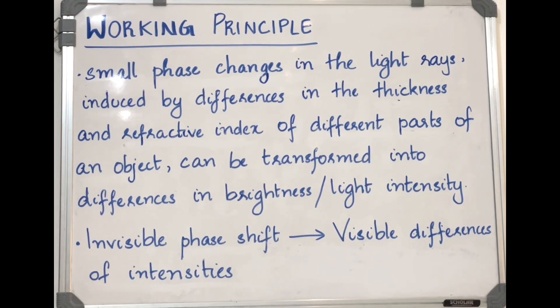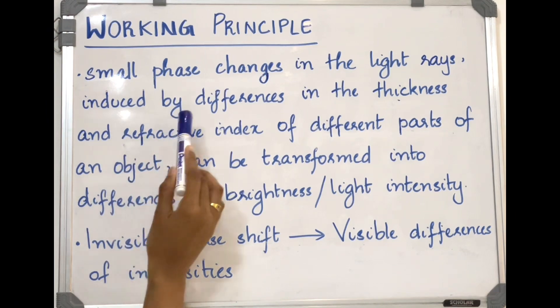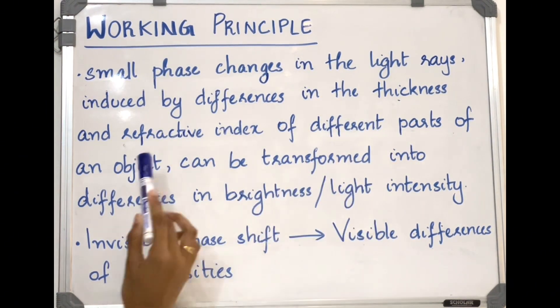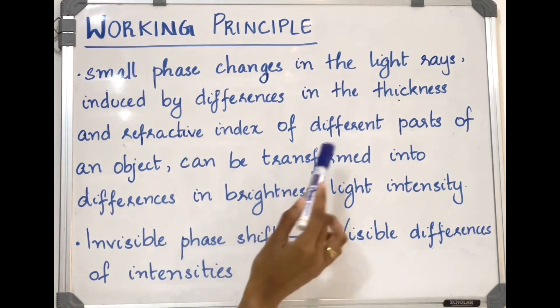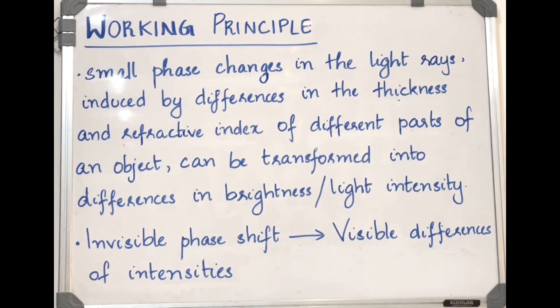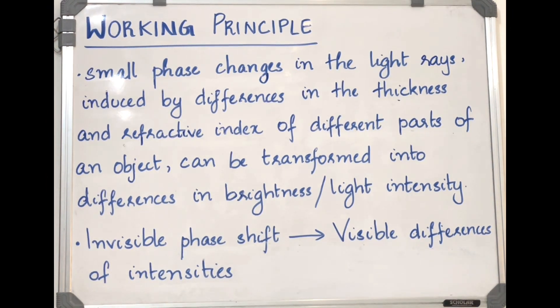Working principle of phase contrast microscope: the phase contrast microscope is based on the principle that small phase changes in the light rays, induced by differences in the thickness and refractive index of different parts of an object, can be transformed into differences in brightness or light intensity. In other words, the phase contrast microscope will translate invisible phase shifts into visible differences of intensity.